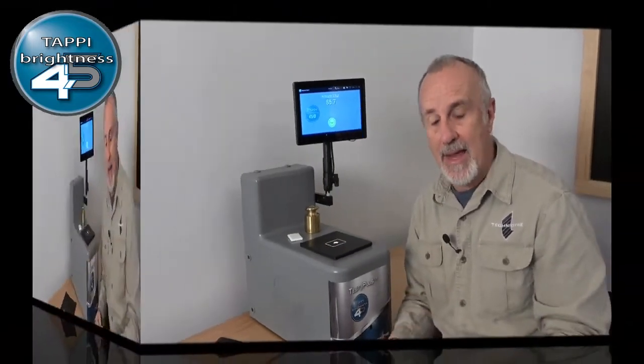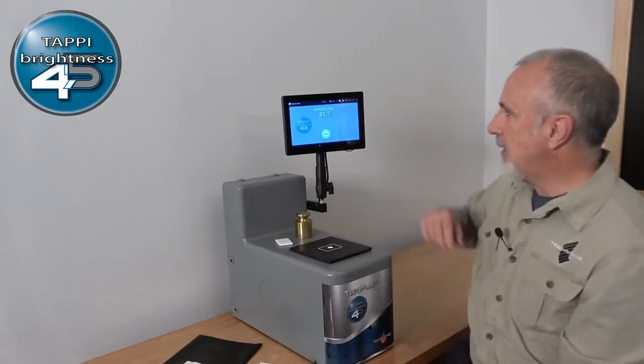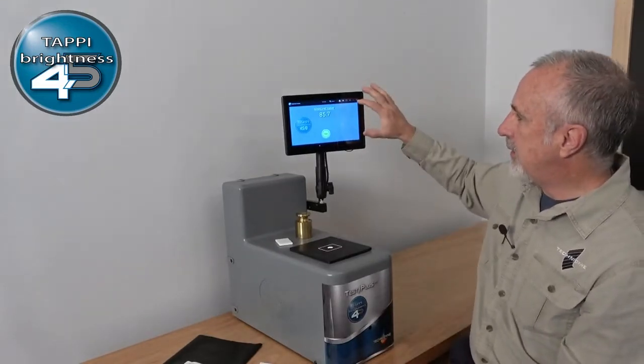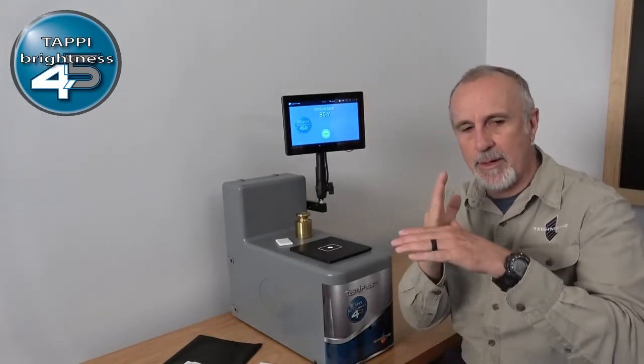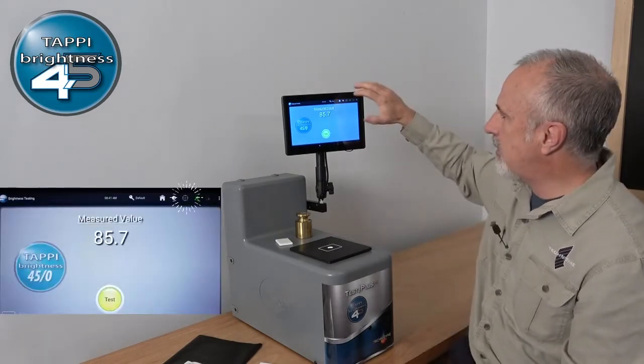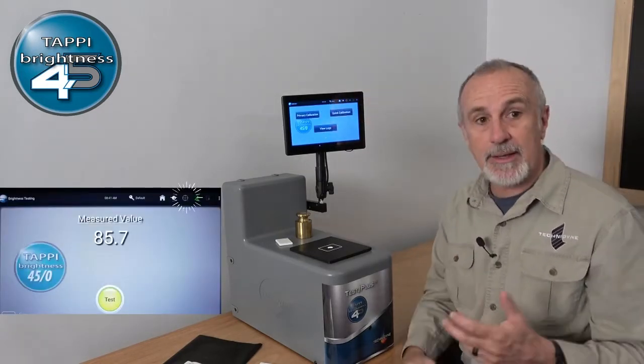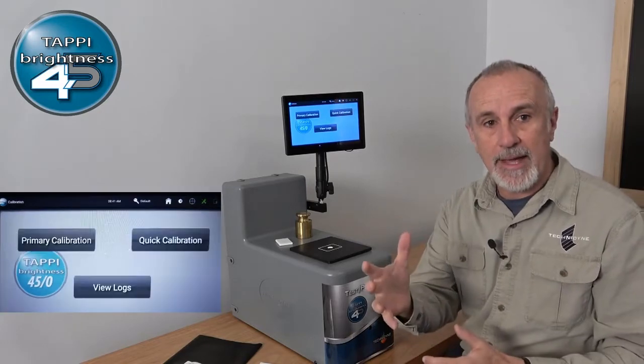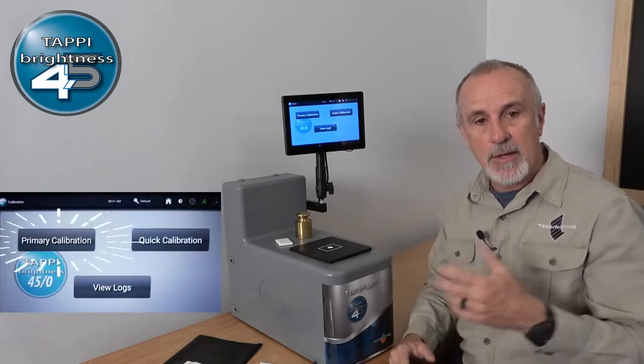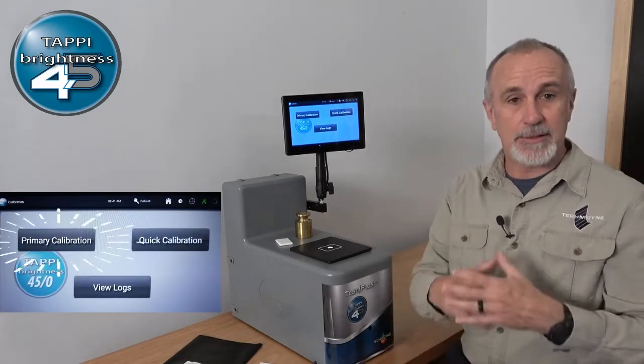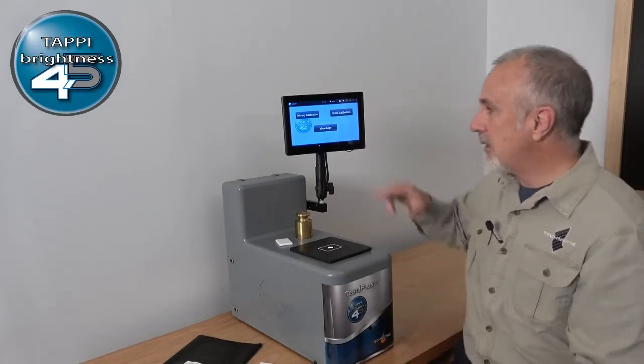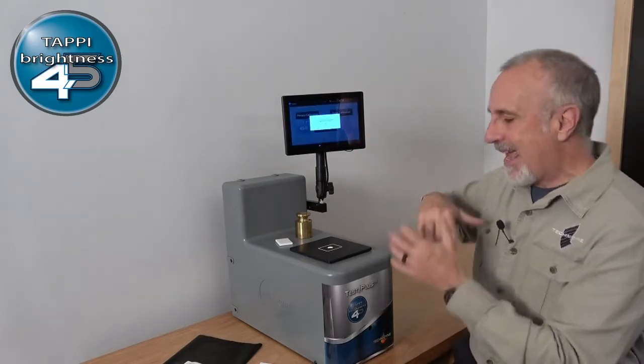So to begin the calibration sequence, up on the home screen, you'll see an icon on the top menu bar that looks like a crosshair. Okay, so you'll select that. Once you select that, you have a choice of doing a primary calibration or a quick calibration. We're going to initially do the primary calibration because that's the first thing you have to do with the instrument. So I'll choose primary calibration, and the instrument will step us through what we need to do next in the calibration sequence.